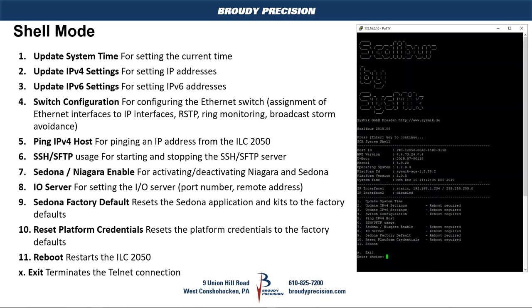In shell mode, looking at it from PuTTY, the menu has 11 items. Various ones are very similar to what you would do with a standard JACE. You can set the system time, IP settings — this device has a four-port switch built in so you can do switch configuration, assign each of the ports, and set it up for ring topology if necessary. You can also ping an IP address to verify that the ILC 2050 can reach other devices.